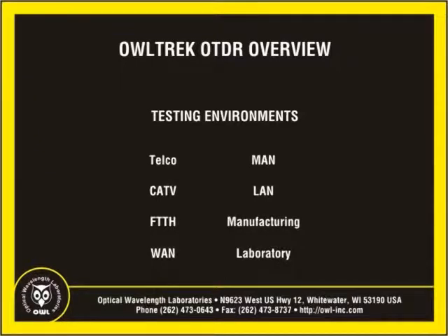Important OTDR trace parameters such as pulse width, index of refraction, and data point averaging are fully user configurable and are accessible through an intuitive menu system. Up to 1,000 traces can be stored in the OWLTrek's internal memory. Powering the OWLTrek is a rechargeable lithium polymer battery that allows for up to 20 continuous hours of normal usage. The OWLTrek is equally suited to testing single mode fibers in many different testing environments, including telco, CATV, FTTH, WAN, MAN, LAN, manufacturing, and laboratories.